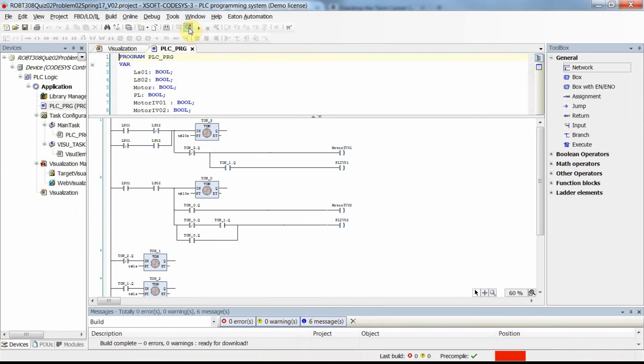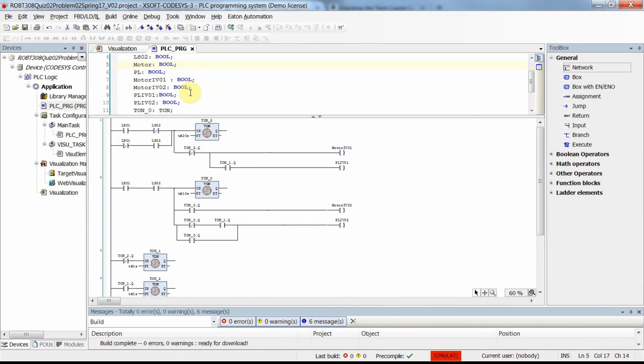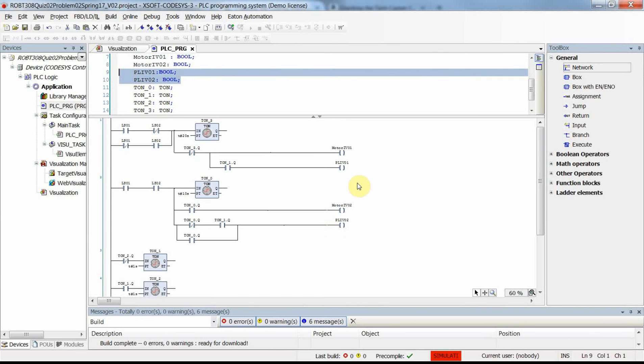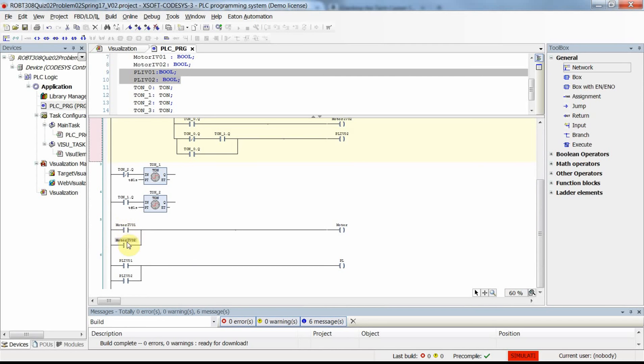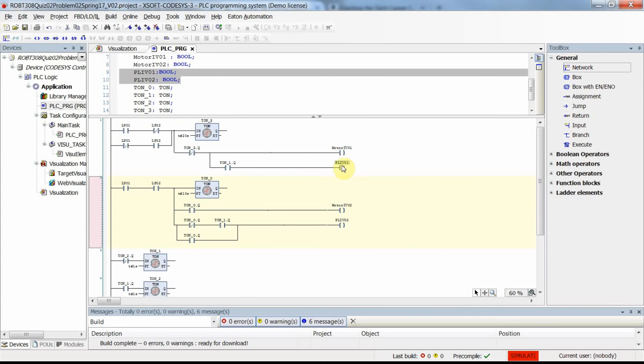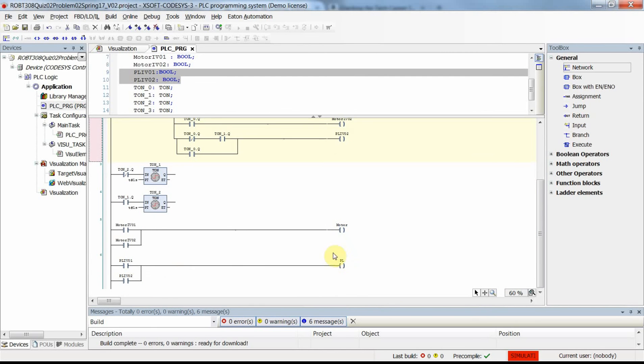Let me explain the changes. By introducing intermediate variables, the first rung now sets motor internal variable 01 as its coil, and the second rung uses motor internal variable 02. At the end of the program these are combined in an OR configuration to determine the motor output state. The same approach applies to the pilot lamp — pilot lamp internal variable 01 and 02 are placed in parallel to determine the pilot lamp output.